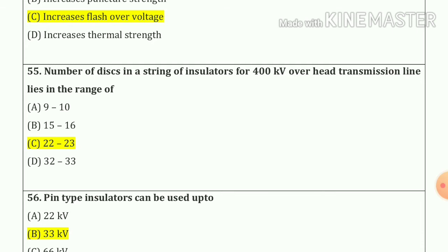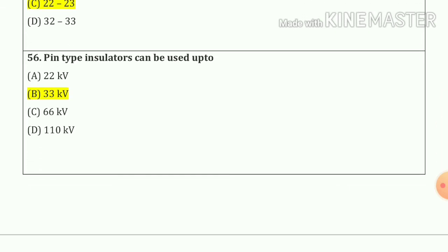Question number 55: number of discs in a string of insulators for 400 kV overhead transmission lines lies in the range of 22 to 23 — option number C. Question number 56: pin type insulator can be used up to 33 kV — option number B.